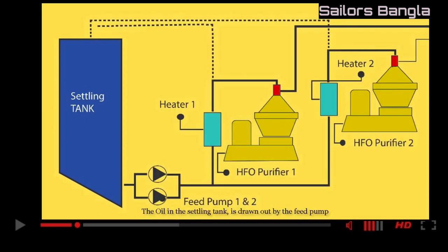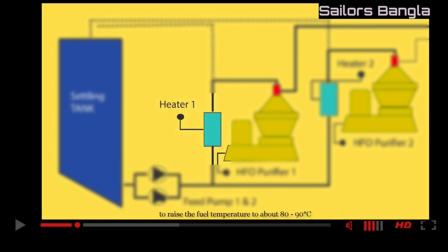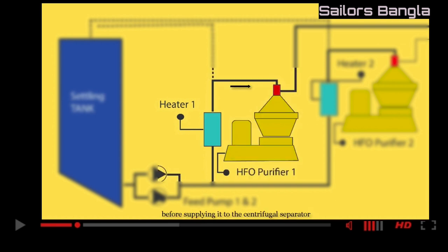The oil in the settling tank is drawn out by the feed pump, which delivers the fuel to a thermostatically controlled heater to raise the fuel temperature to about 80 to 90 degrees Celsius before supplying it to the centrifugal separator.